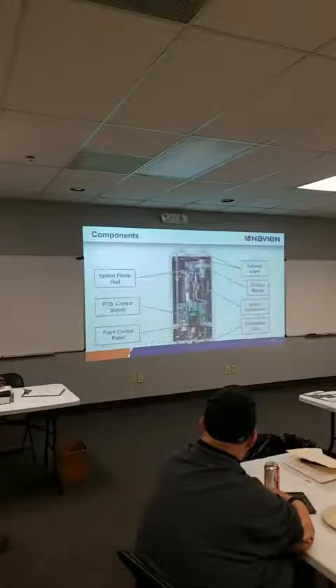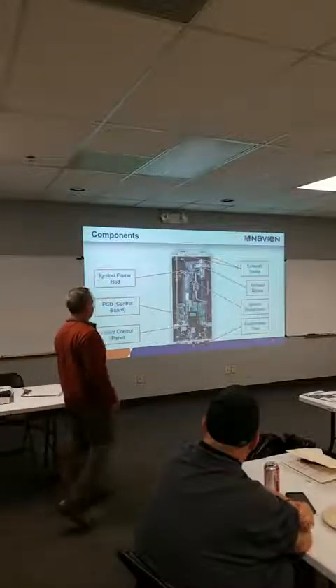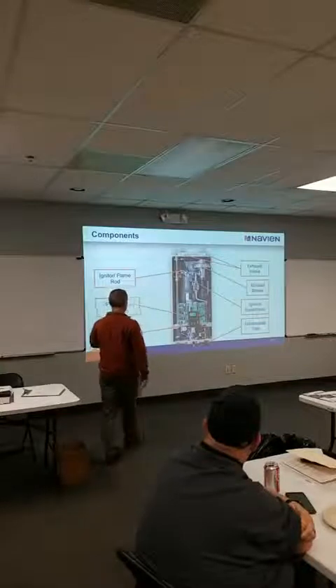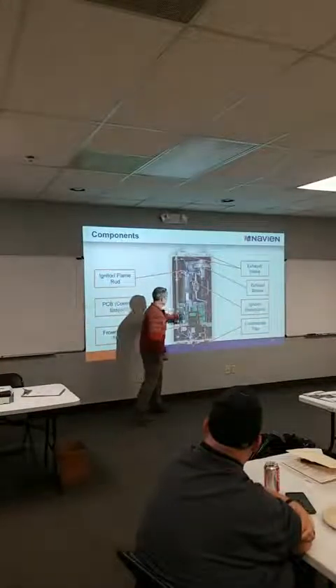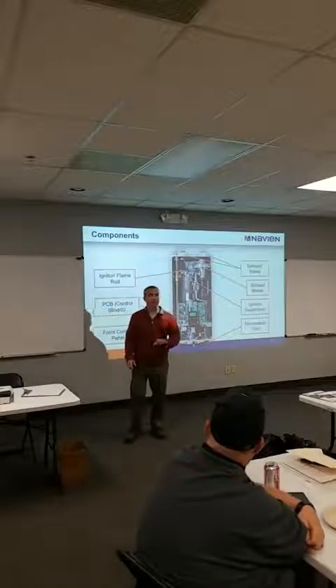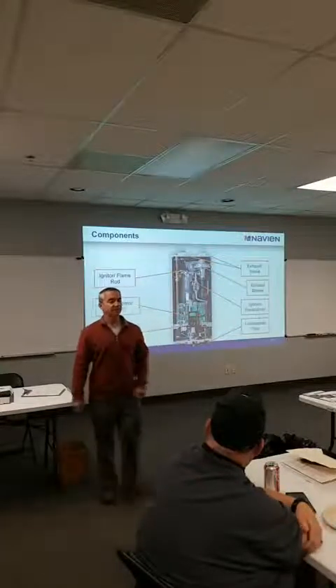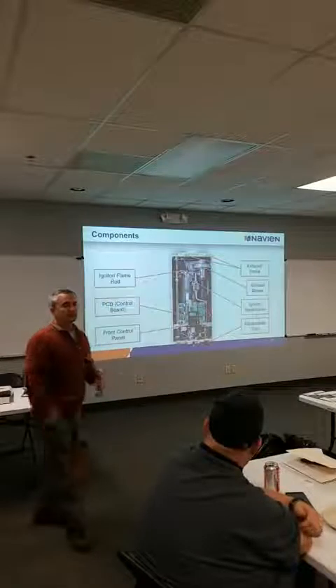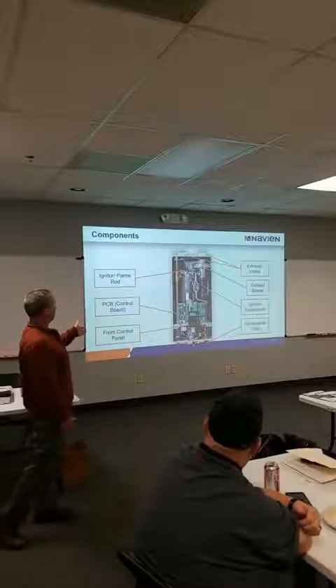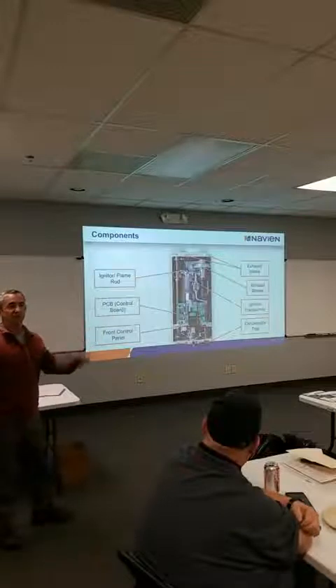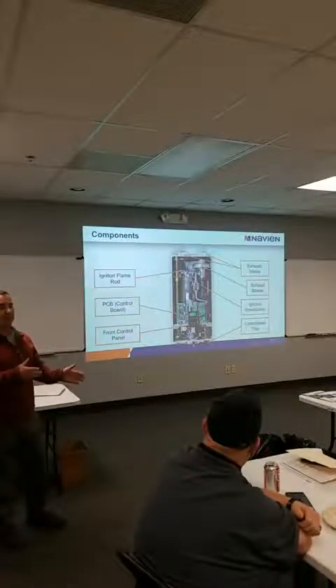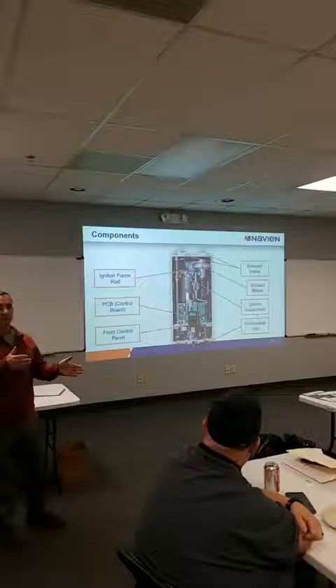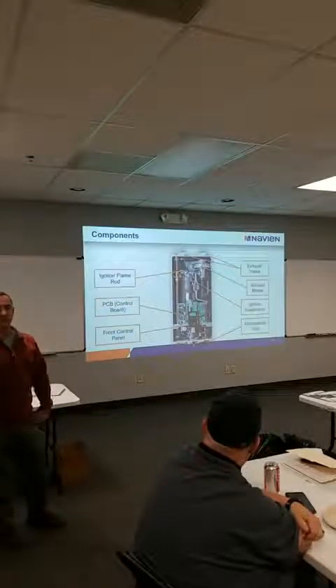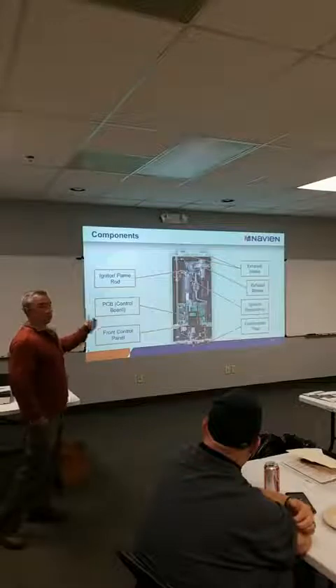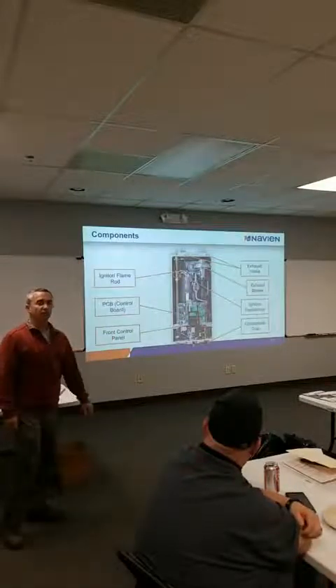So you've seen all these pictures before. The inside just looks a little different than the NFB boiler because it's a combi. And it's got the same board, same keypad, all the same installation rules apply that we just talked about. So they're trying to make it simple. The big difference in this combi is it's larger, 175 and 200. So we got combi from 80 to 150, and then we've added a 175 and a 200. Plus we're giving you commercial application, commercial warranty with the NFC combi.